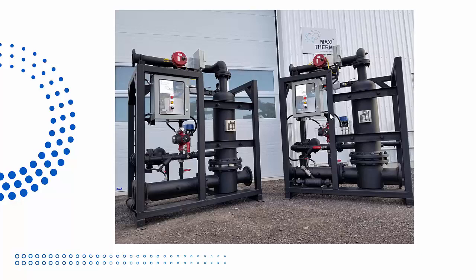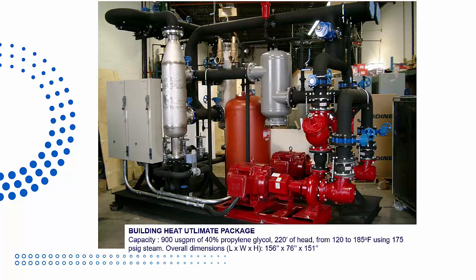This is another system. We do the MCU model. It can be for building heat or considered as a semi-instantaneous water heater. Another picture, of a unit we shipped many, many years ago. Everything is accessible, removable, repairable, electric panel. Everything is on it. It's a 20 million BTU process, which means 600 horsepower. Again, it's a redundant system. This mechanical room right there is 13 feet long, 6 feet wide. That's all you need for a 20 million BTU process.